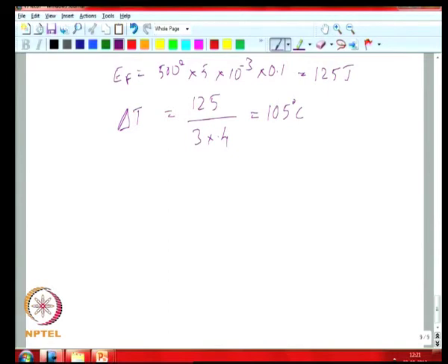then during fault if you have a rise of 105, it is getting close to the point where it is damaging the insulation. So, you could consider a few options at this point. One option is maybe you could look at a protective device which can operate in a quicker manner, maybe 3 cycles rather than 5 cycles. Many times you do not want to design your own special circuit breaker, you want to use the commercially available device. So, you might be restricted in terms of how quickly it acts. The commercially available device might be 5 cycles, might be what its instantaneous trip duration is.